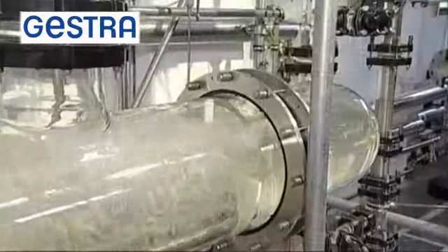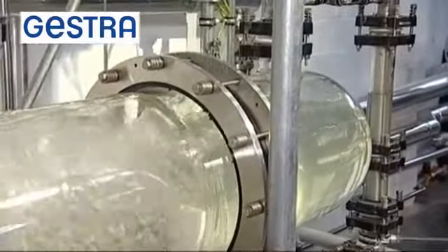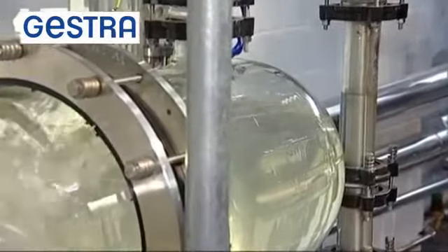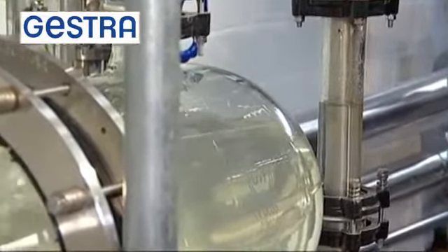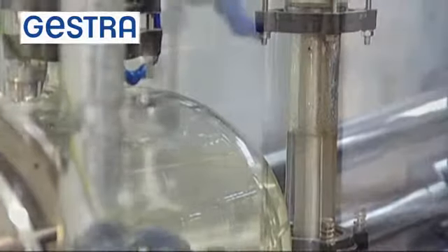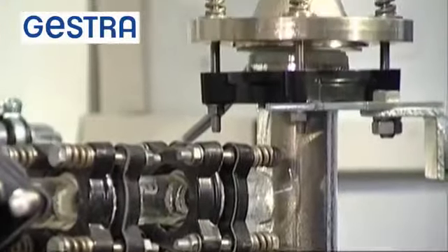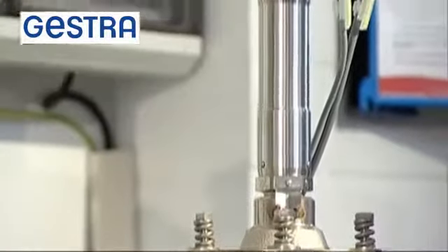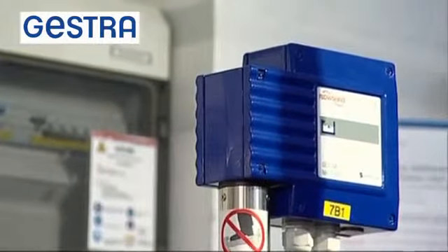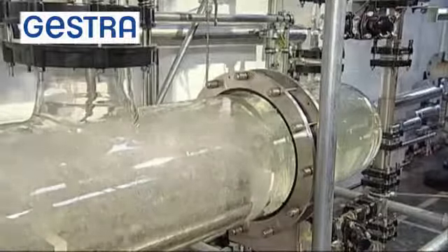Here it becomes clear just how important exact level measurement with only a very small control deviation is for steam boilers. An external measuring pot provides optimum measurement results. No matter how turbulent the surface in the steam boiler, the water level in the measuring pot will remain calm. Measurement takes place by means of a capacitive sensing system, delivering a stepless 4 to 20 mA signal. In this way, the water level in the steam boiler can be controlled with a deviation of only 1 to 2%. Such precise regulation is not possible if conductive level probes operating according to the on-off control principle are used.